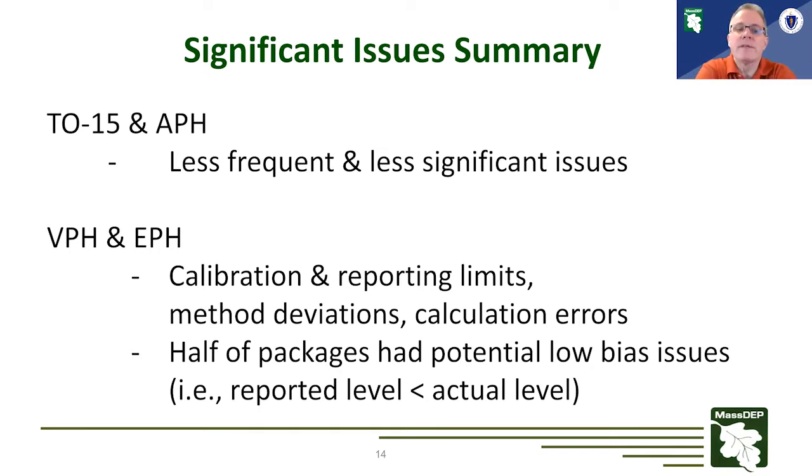For the air methods, the TO15 and the APH studies, overall the labs did very well. Their CAM compliance was pretty universal. There were less frequent and less significant issues with those methods. And so they demonstrated that they have a good understanding and practice of performing those methods. The VPH, EPH methods, however, did have some issues, mostly to do with calibration and reporting limits, in addition to method deviations and calculation errors.